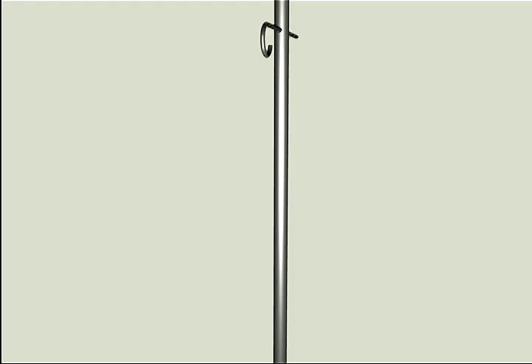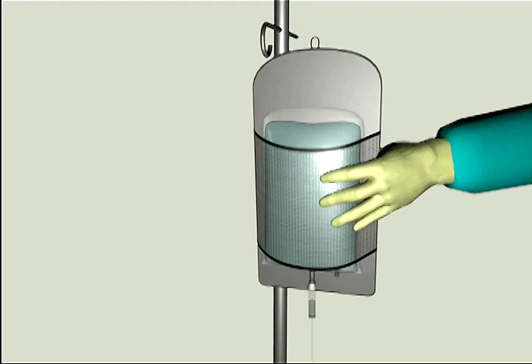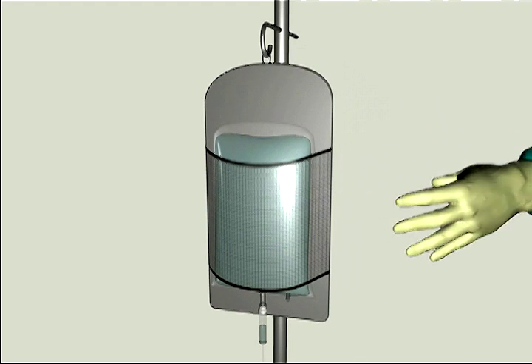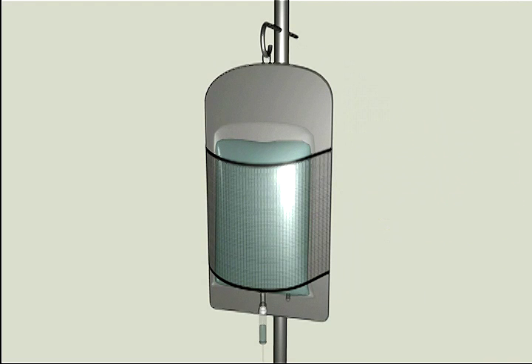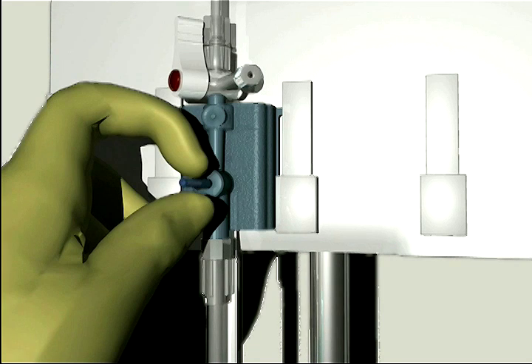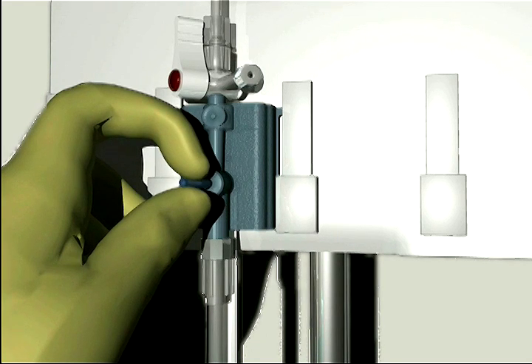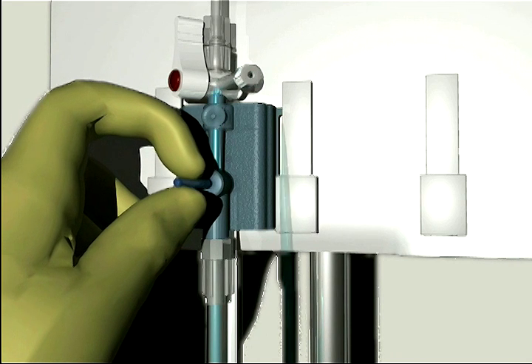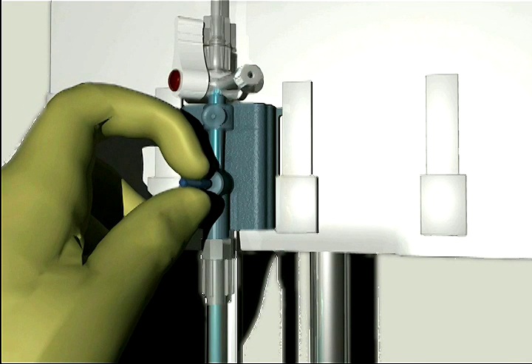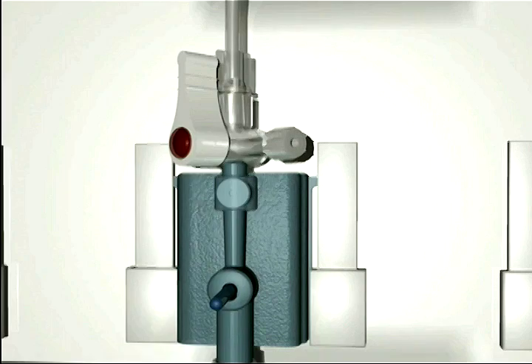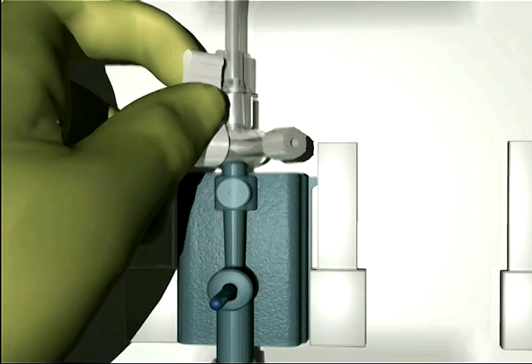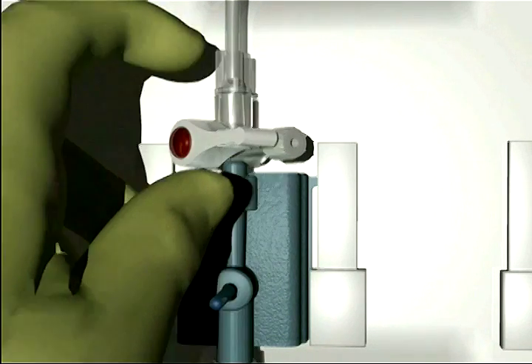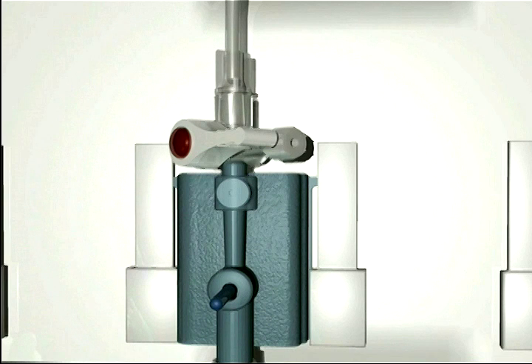Insert the IV bag into a pressure infuser bag and hang on an IV pole. Do not inflate. Pull the snap tab flush device to deliver the flush solution through the TruWave transducer and out through the vent port's vented cap. Remove all air bubbles. Close the vent port by turning the stopcock towards the cap.